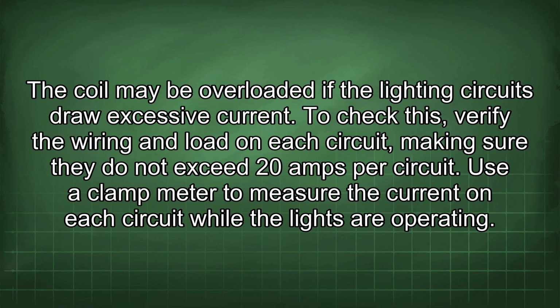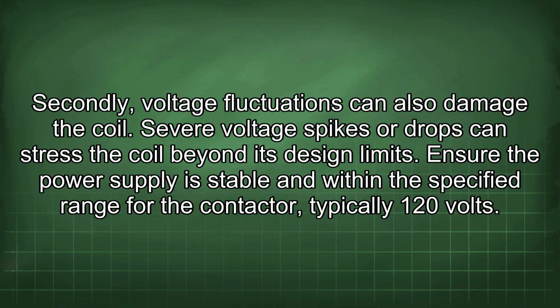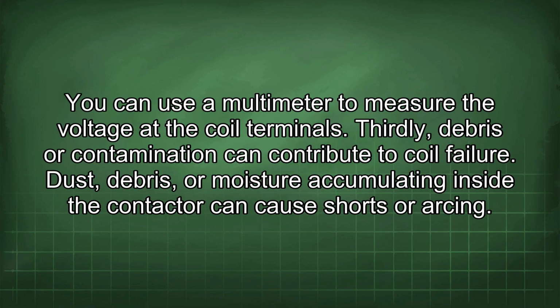To check this, verify the wiring and load on each circuit, making sure they do not exceed 20 amps per circuit. Use a clamp meter to measure the current on each circuit while the lights are operating. Secondly, voltage fluctuations can also damage the coil. Severe voltage spikes or drops can stress the coil beyond its design limits. Ensure the power supply is stable and within the specified range for the contactor, typically 120 volts. You can use a multimeter to measure the voltage at the coil terminals.